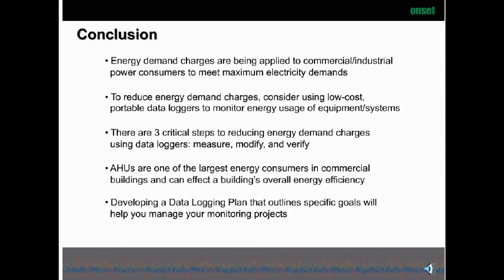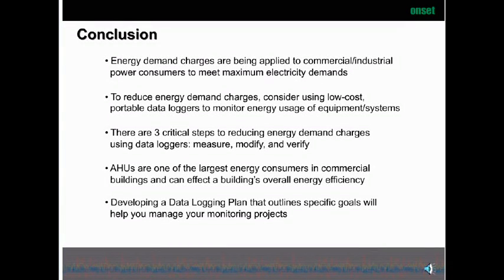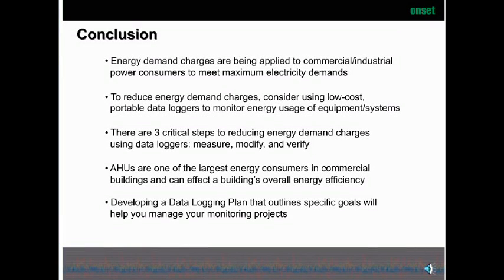In conclusion, energy demand charges are being raised across the country for commercial and industrial power consumers. You need to have a plan and a means to reduce these additional energy costs. One of the ways is to use low-cost portable data loggers to identify equipment that is causing these charges in your facility. There are three steps to reducing energy demand charges using data loggers: you measure, then modify the equipment, and then verify that the modifications have taken effect. AHUs are one of the largest energy consumers in a commercial building, and they can affect your building's overall energy efficiency, as well as chillers, boilers, and other large pieces of equipment.